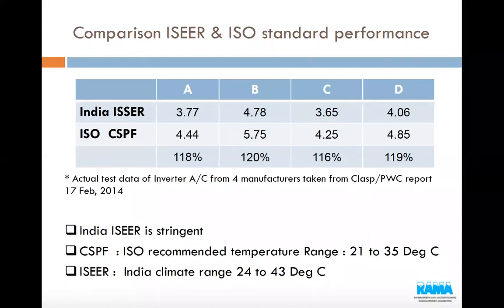If you look at the same air conditioners, four samples were selected and tested as per Indian standards for ISEER, and as per ISO, which is recommended by the standard. We can clearly see that if we pick any Indian unit today and test it as per ISO to arrive at CSPF, it will be about 116 to 120% more efficient. I'm sure this number will be slightly better now compared to before. This happens because the temperature zones are different in computing CSPF and ISEER.